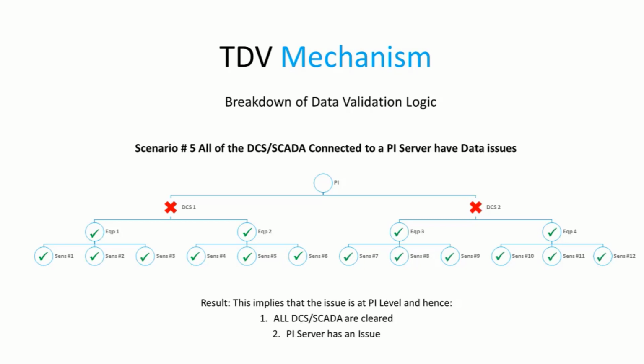If we look at scenario number 5, if all the DCS or SCADA connected to the PI server have data issues, meaning we're not getting data from the DCS, that means it's the PI server. This implies the issue is at the PI level, and hence the DCS are cleared, and the PI server has the issue, not the interface, since we have good data under the interface. So this just shows the mechanism: the PI system will be flagged, all the DCS are cleared, and the PI server has the issue.